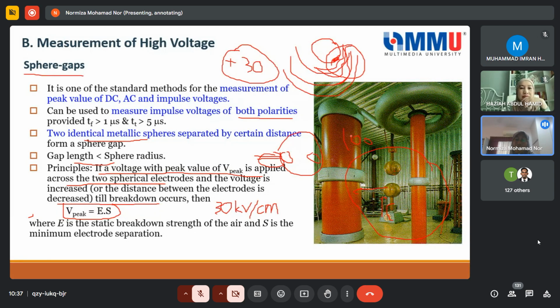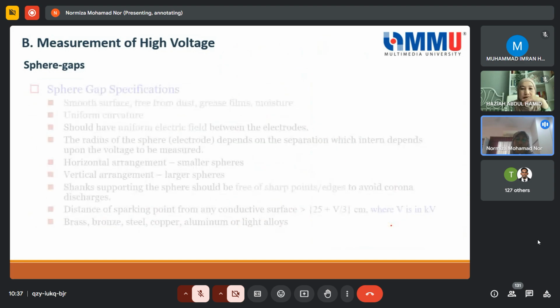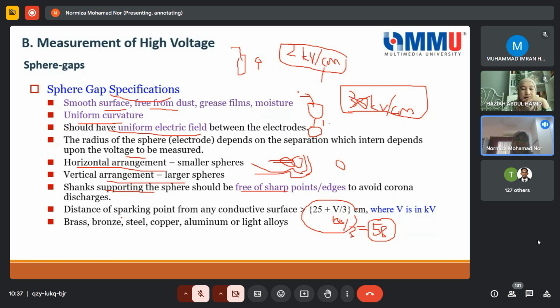So if I apply 100 kV, the clearance from the ground and the clearance from the surroundings would have to be at least 60 cm. So you can see, it's around that actually. This is how we determine the distance for the sparking point for the sphere gap. But other equipment has a different formula. As I mentioned, for our high voltage lab, this is what we normally use, 2 kV per cm, or if the equipment is more dangerous, prone to spike or flashover, we use even lower, like 1 kV or 0.5 kV per cm.